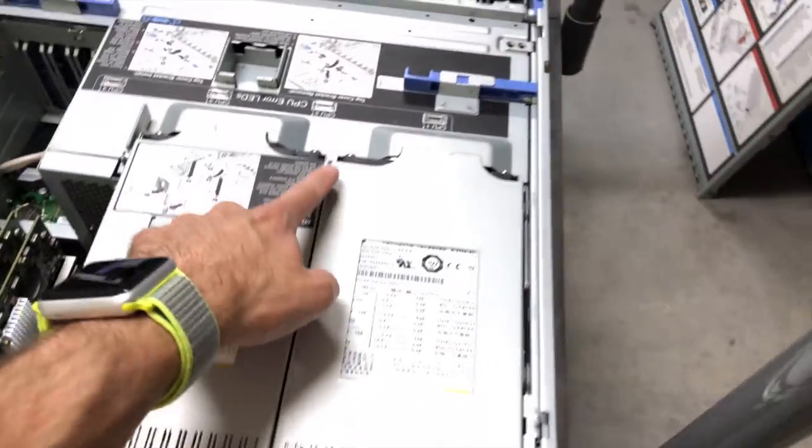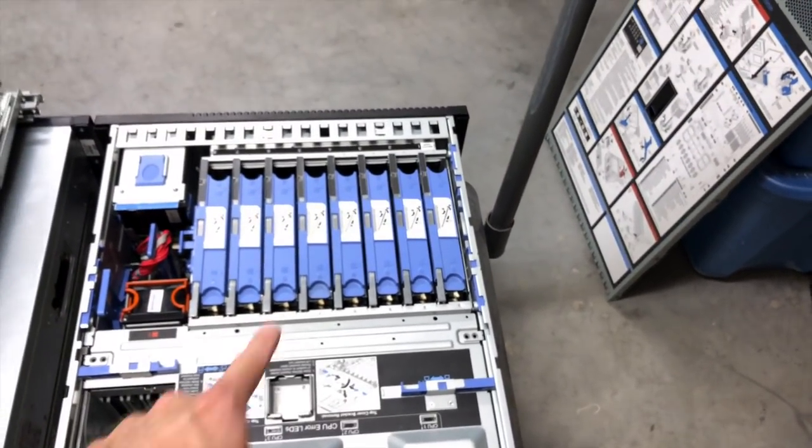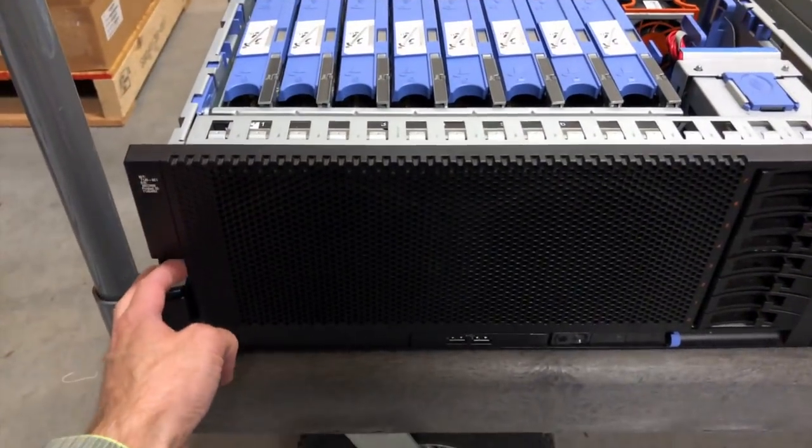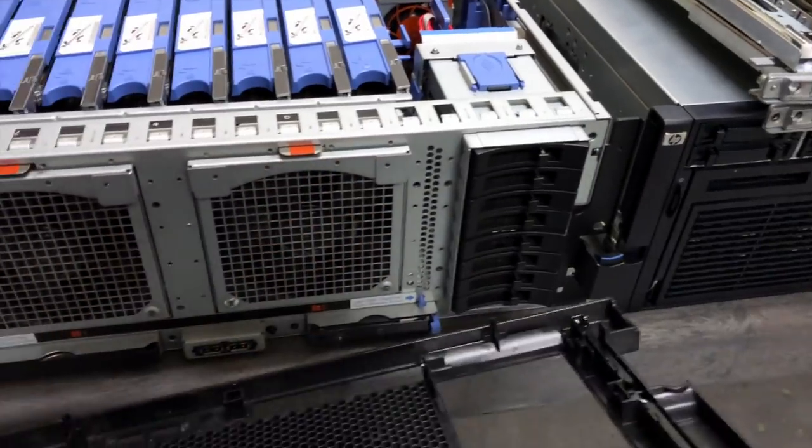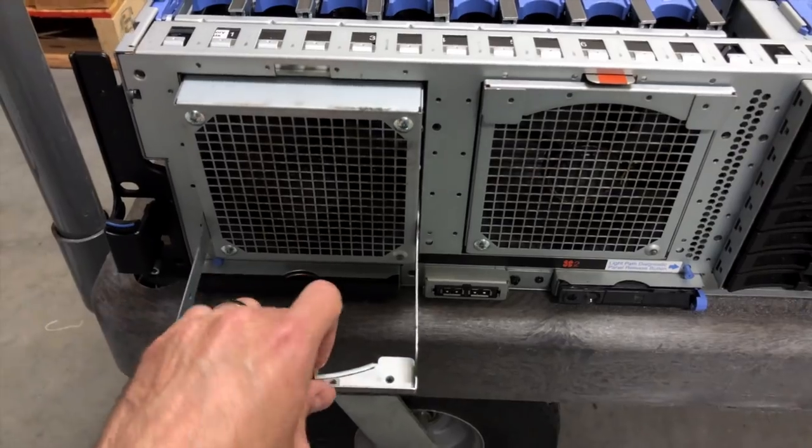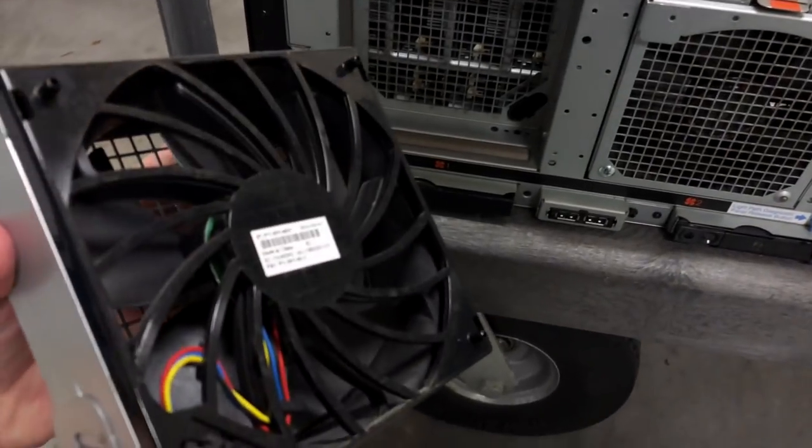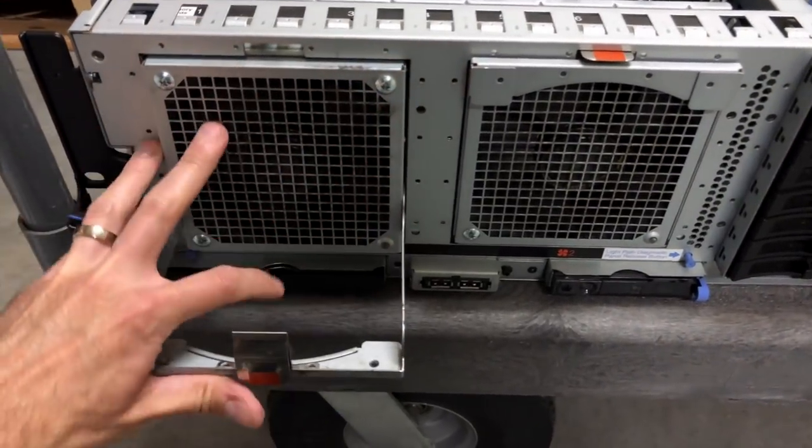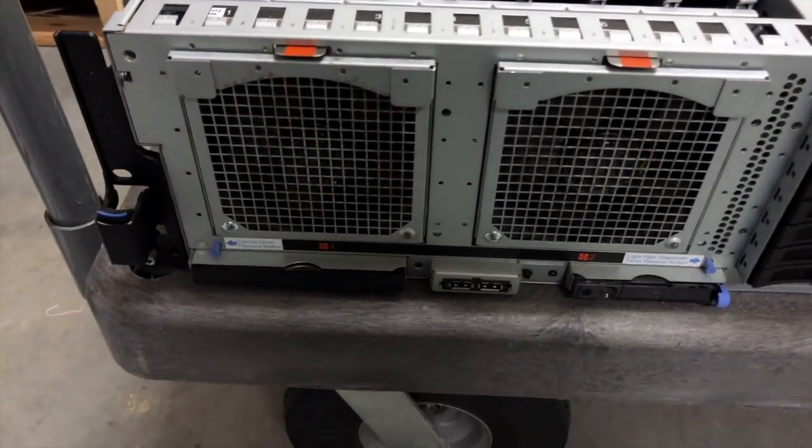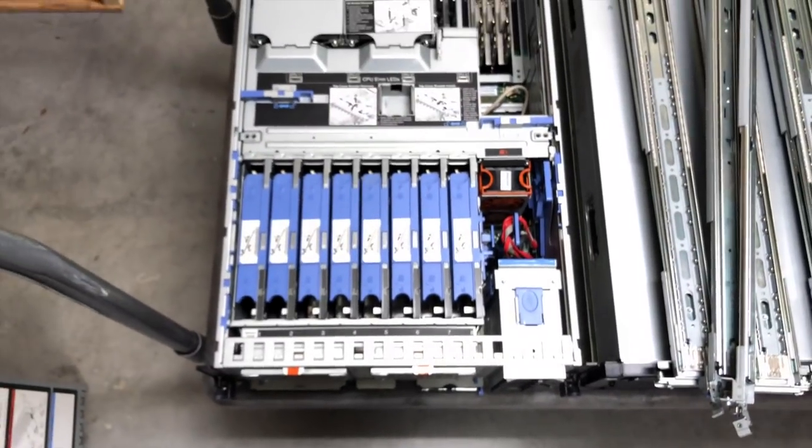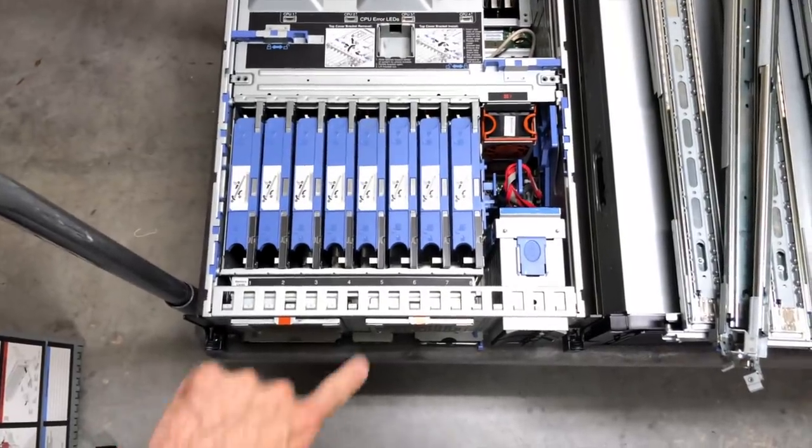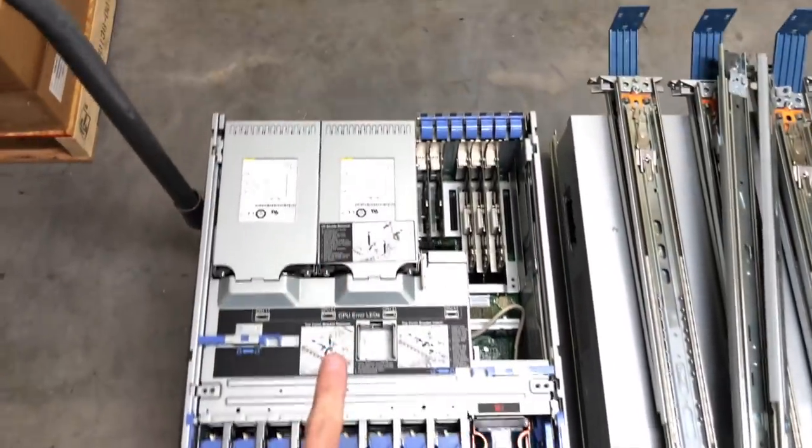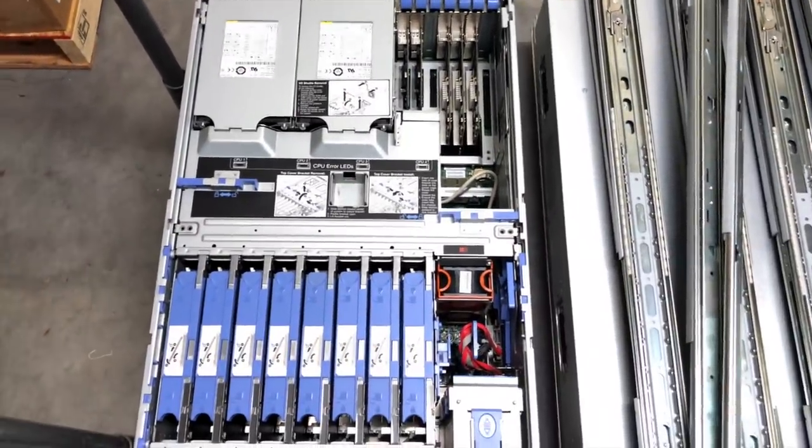There are various fans throughout the system. The power supplies themselves have fans built in. And then what cools the RAM and the CPUs, since those don't have fans built in, is around front here. You can pop these tabs. The front panel comes off and then there are fans underneath here. Of course, these are hot swappable as well. That's what basically pushes air through the front of the system and out the back. Servers are generally front to back airflow. So all the cool air in the server room goes in through the front, gets pushed through all the components, and then the hot air comes out the back to get sucked back into the air conditioner and circulated around.